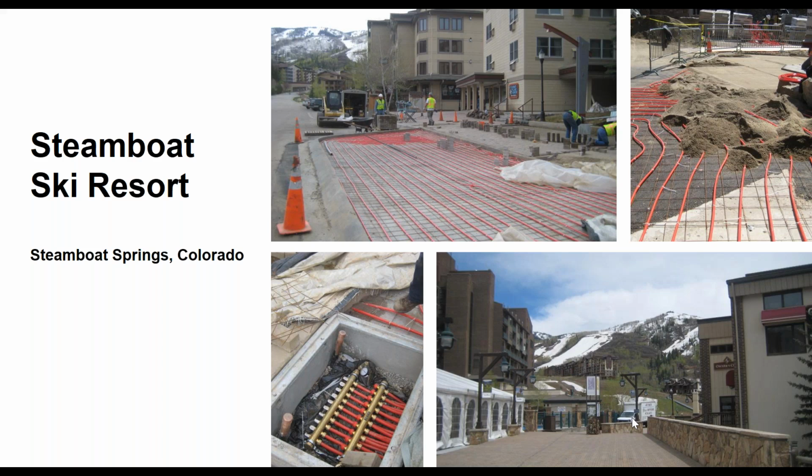One of the cool things that I saw wholesaler Greg Burney in Colorado do one time is that there was kind of a mix up where they put the snow melt sensor and the concrete guys pulled the pipe really far away from the sensor. So when it went into operation, there was kind of a big snowball on top of the sensor that never melted clear. A cool troubleshooting tip that he had is that he was trying to figure it out. They went back and they switched the supply and the return pipe. They had to add a little extension there, I guess, to make it work. But then the way that particular routing of the pipe went, they ended up getting the warmest pipe to go right by the sensor first, just kind of by luck, and got themselves out of a bind there instead of having to core drill and move the sensor or something like that.